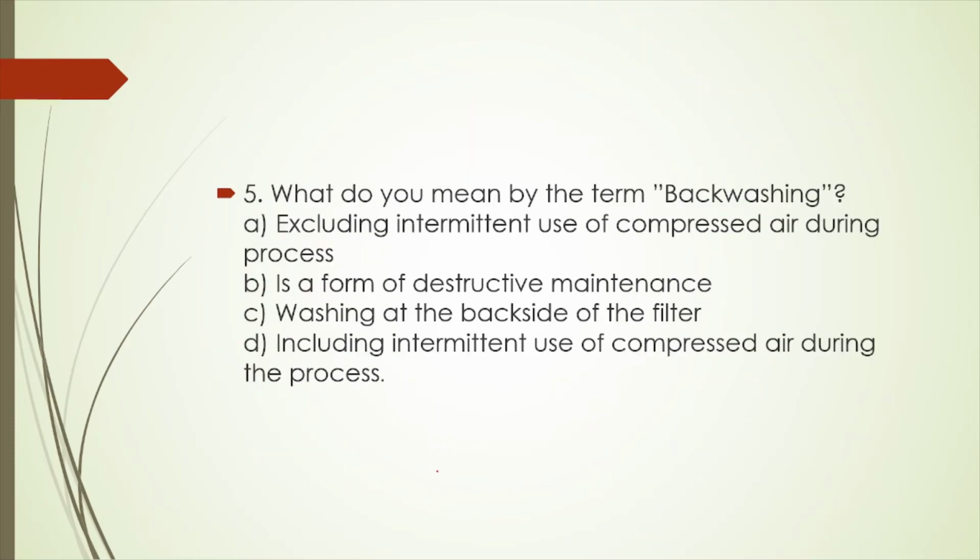What do you mean by the term backwashing? Now you have to know what is backwashing, alright, and where is it used. Mostly it is used for filtration of water, alright. So in terms of water treatment, including water purification and sewage treatment, backwashing refers to pumping water backward through the filter media, sometimes including intermittent use of compressed air during the process.